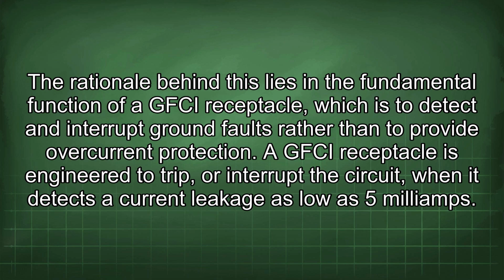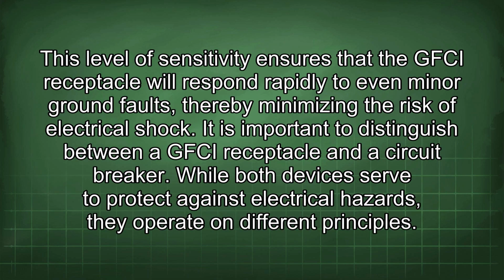A GFCI receptacle is engineered to trip or interrupt the circuit when it detects a current leakage as low as 5 milliamps. This level of sensitivity ensures that the GFCI receptacle will respond rapidly to even minor ground faults, thereby minimizing the risk of electrical shock.